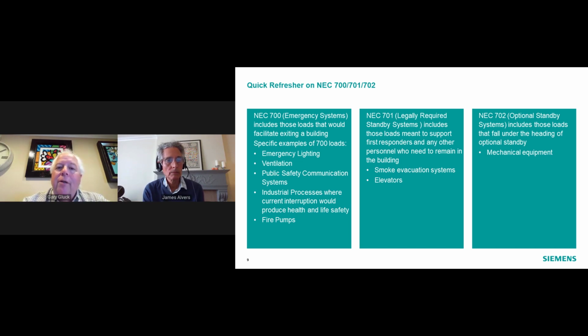And then we're also going to throw in, in a non-commercial sense, certain industrial processes where current interruption would be pretty disastrous. So that's 700. 701, legally required, those are going to be the systems that need to be functioning for people that need to be in the building. So whatever personnel might include first responders, other firefighters, other emergency personnel. So here's where we're going to find smoke evacuation systems. I'm also putting elevators in this section. Some of you might say, wait a second, elevators are part of the emergency system. There's a certain debate and it's really not a debate, it's really what is applicable or appropriate for a specific building. When you have elevators that are going to be needed for assisting the first responders, that's going to have the tendency to move those systems into 701.